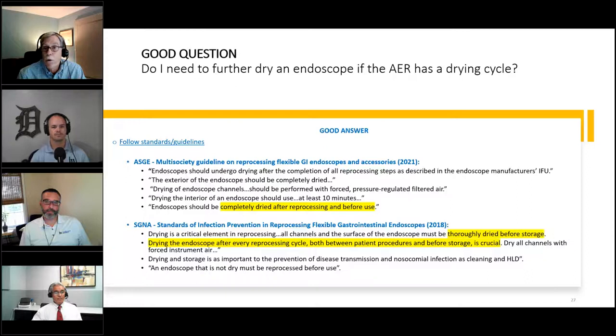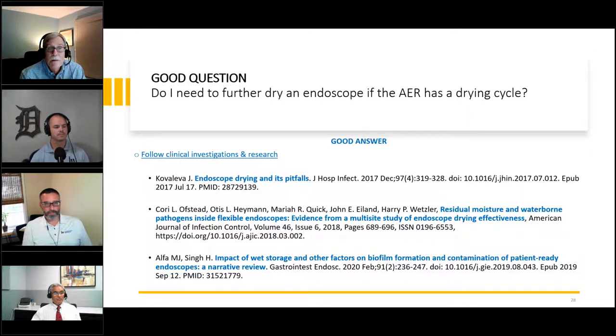They reference forced pressure regulated filtered air for at least 10 minutes. SGNA similarly highlights the need for thorough drying before storage or reuse. They emphasize that an endoscope that's not dry must be reprocessed before use. The common thread here is active filtered air drying every time, whether the scope's headed for storage or to the next procedure.